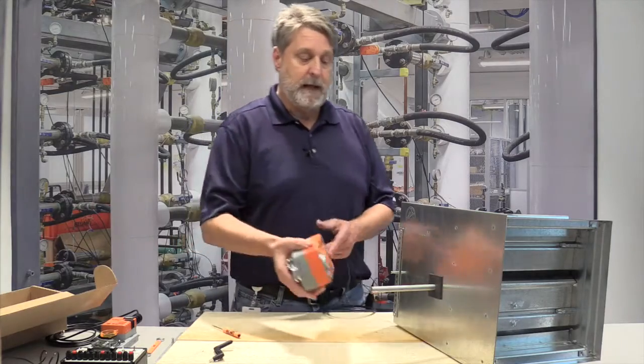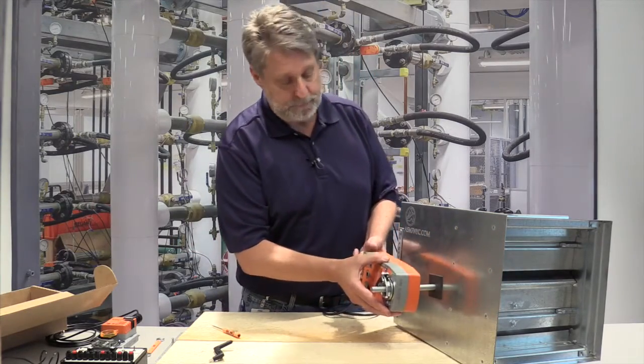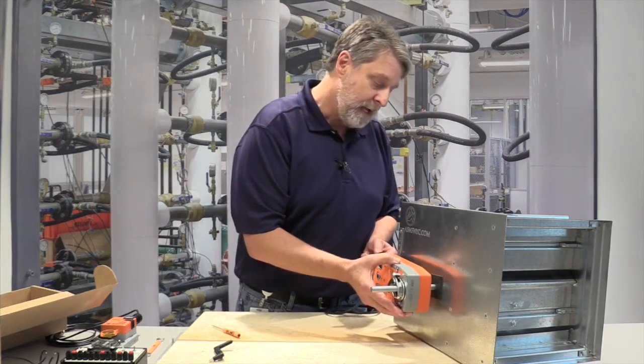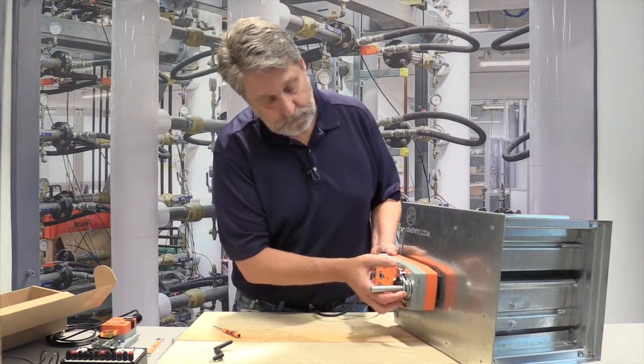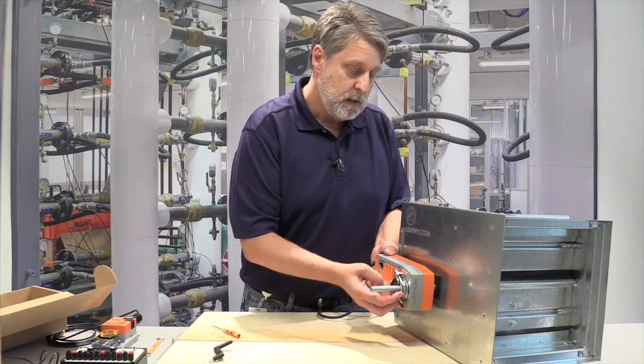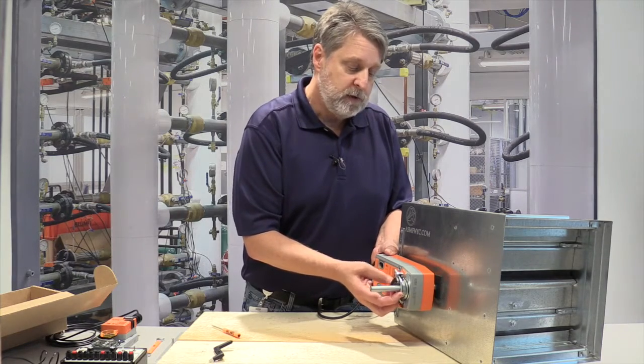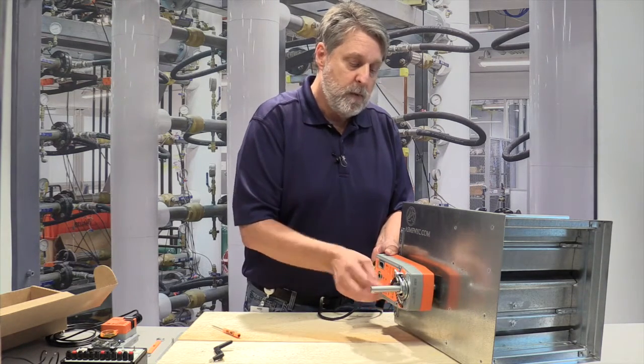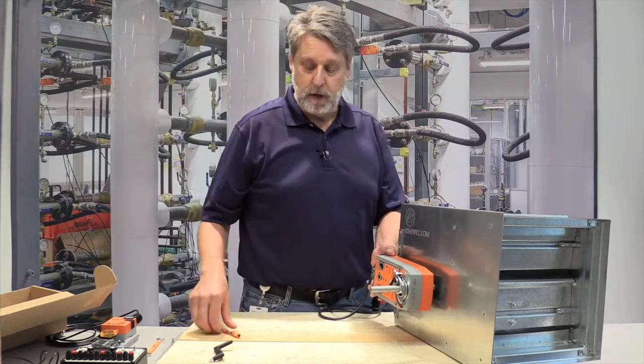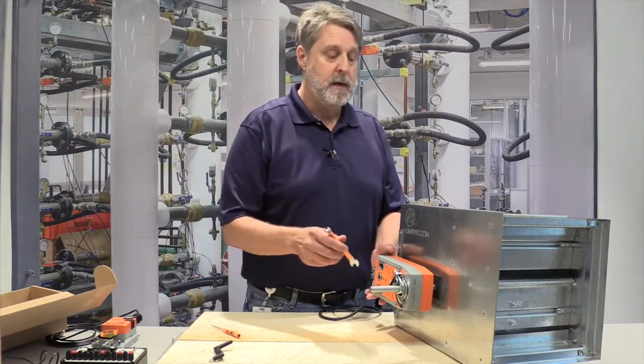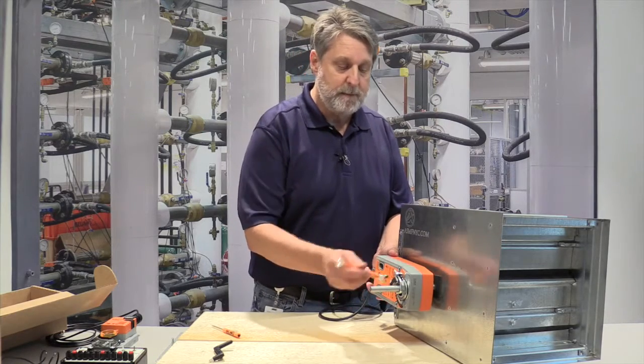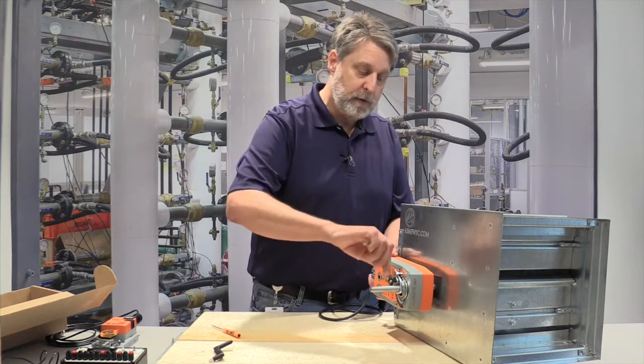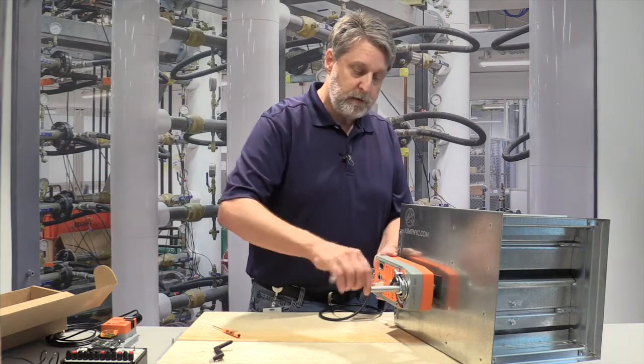I'm going to go ahead and mount this on the damper assembly so we can test it. When you're tightening this in the field, we want to have between six and eight foot pounds of torque on these nuts. Because I'm doing a demonstration today, I'm just going to snug these up.